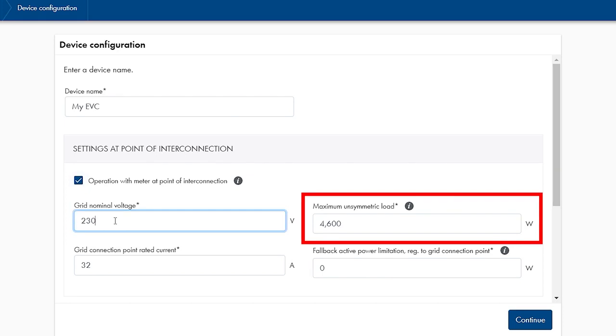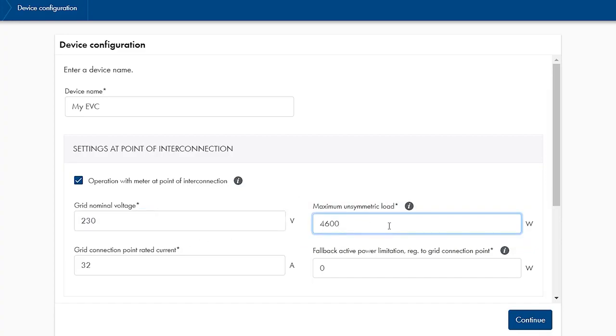Next, type in the country-specific maximum unbalanced load limit. 4600W is relevant for Germany. If there is no unbalanced load limit for the country, the maximum power permitted per phase based on the local conditions such as cable cross-section must be specified here. The SMA EV charger allows a maximum of 7400W per phase.